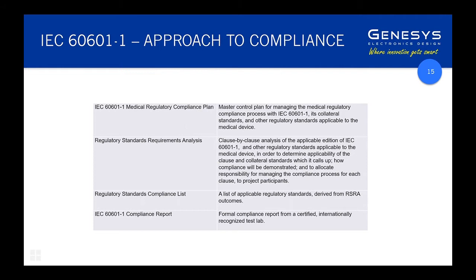You can use the clause-by-clause analysis in interfacing with your compliance laboratory — showing them your view of what you need to comply with. They may come back with a contrary view, but it gives you a sound foundation and gives the compliance lab confidence that you know what you're doing. Engage with your test lab early and often. There is also an issue to consider: if you want to apply the NRTL mark to your product, you may find you're constrained to use a laboratory that can apply that mark, and they may insist on doing some compliance assessment themselves.